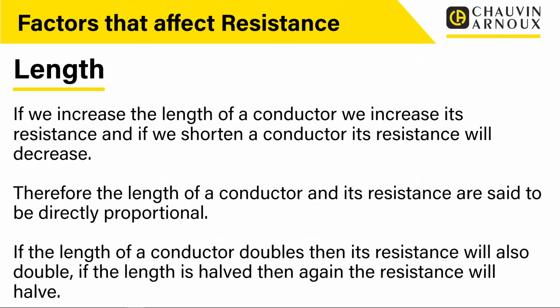So as we measure over a longer distance, resistance readings will increase, and in a shorter distance they will decrease. And this is why it's quite important when you're positioning your test probes, because you are measuring between those probes. So again, it is important that we know what we're measuring, because if we position the probes in a different position, we will get a different resistance reading just based on the fact that we're measuring a different length of conductor.